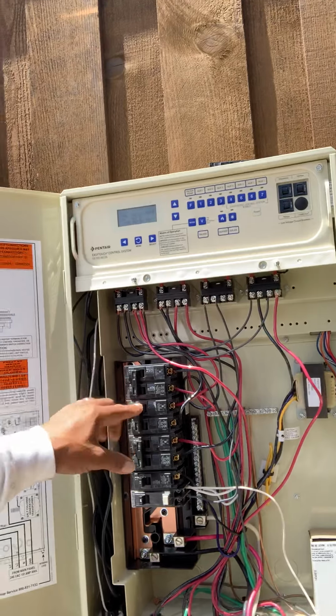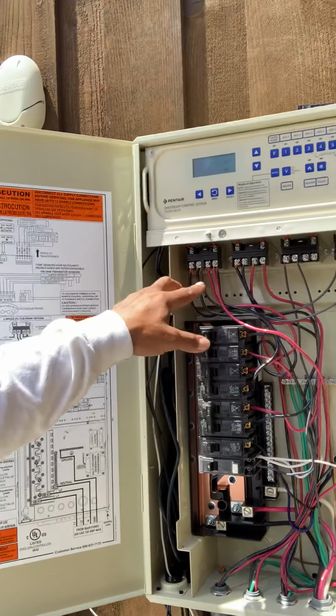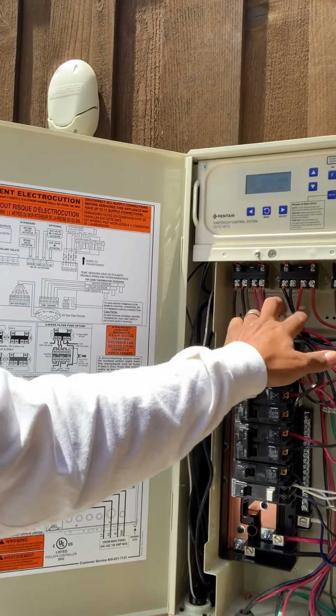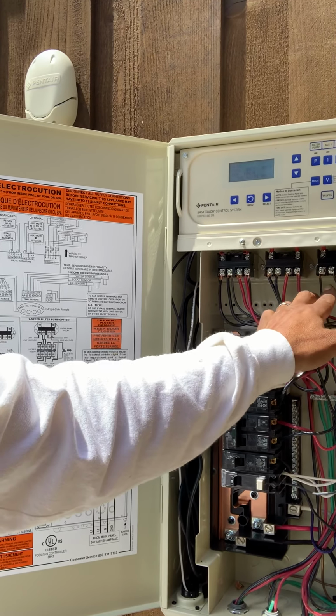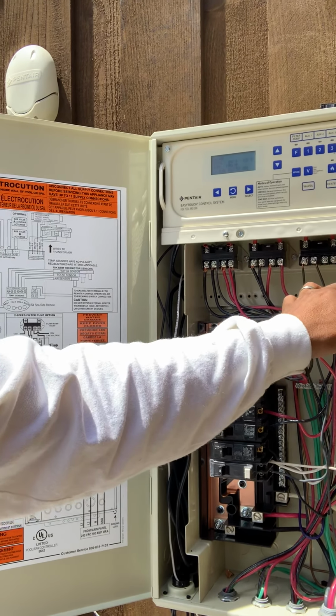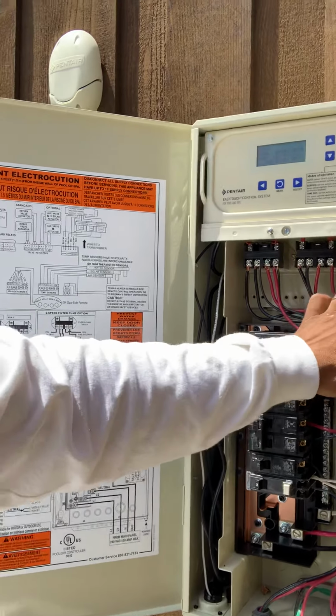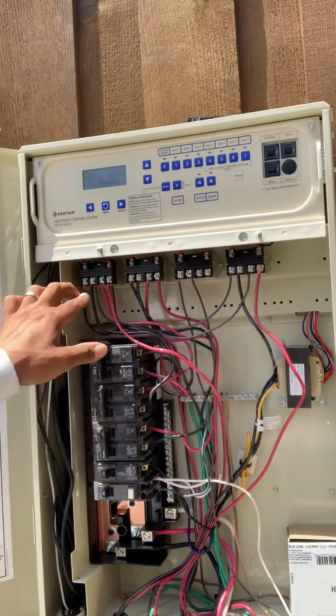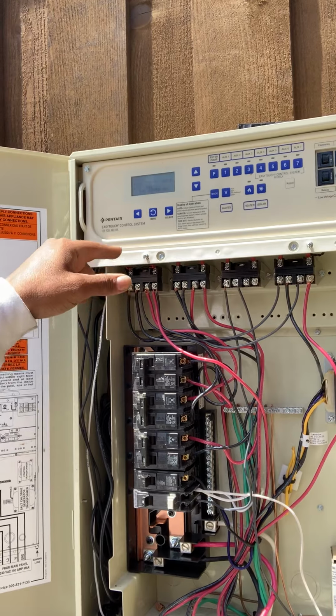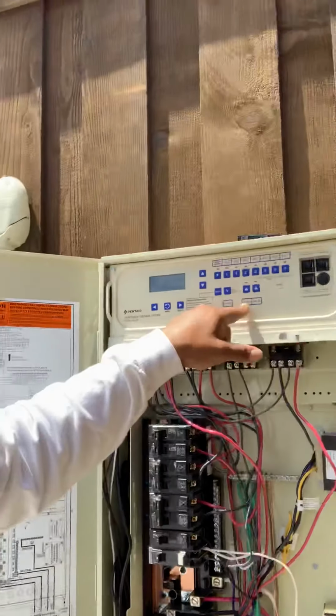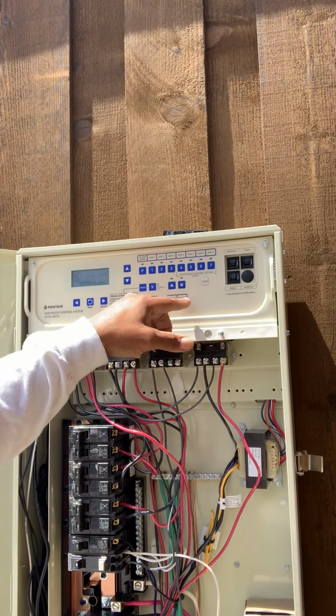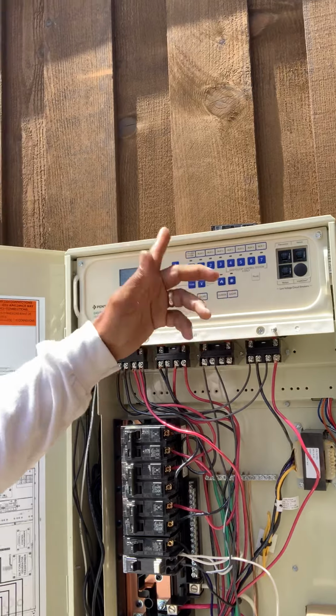So you take all the lines and you bring them to your line side, which is these two right here, these two are always your line. This is your line, that's your load, that's your line. This is your load, this is your line. But these two lines for the cleaner pump will come off this, because this filter pump has to be on first, like I told you in one of my pool episodes, for like 15 or 25 seconds before it goes on. So I don't know, and if you come here and you turn on heater, or whatever, the guy knows how to do that.